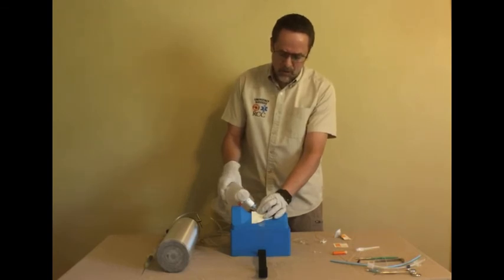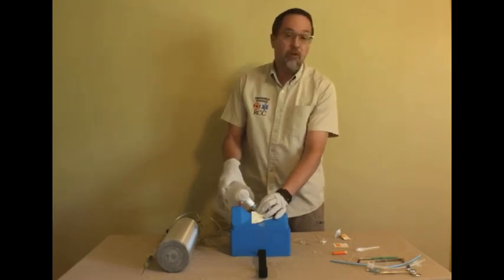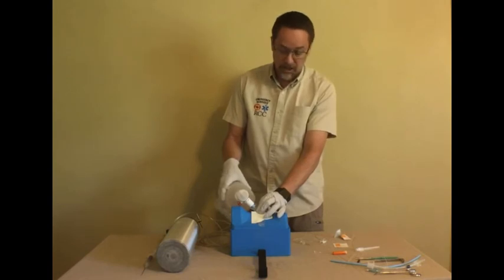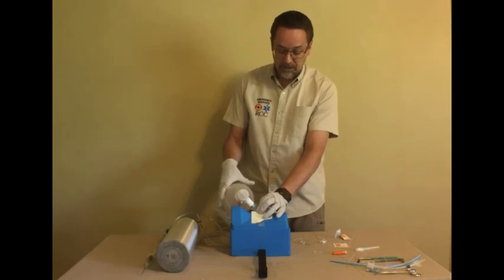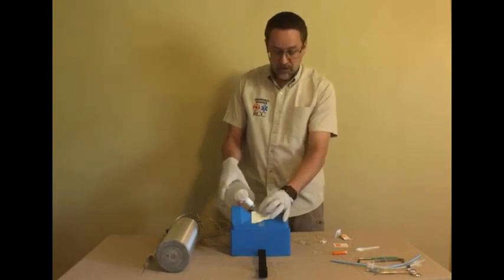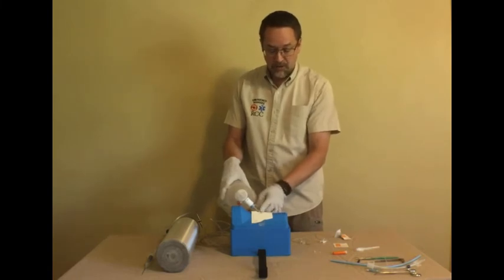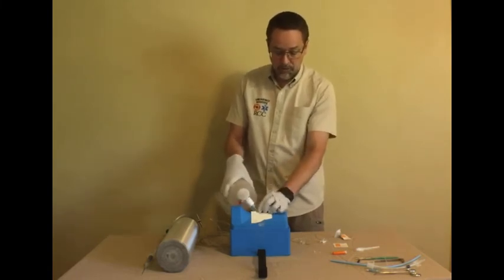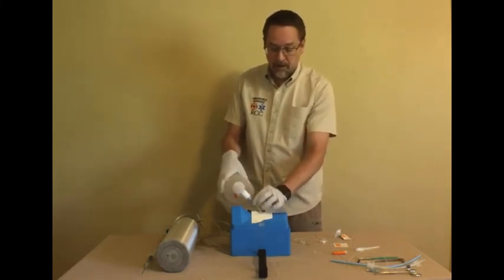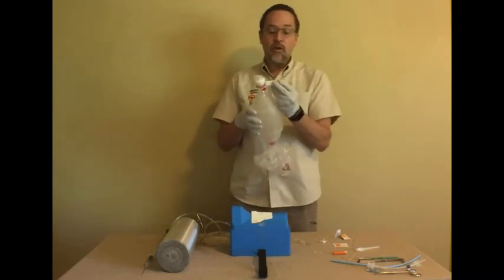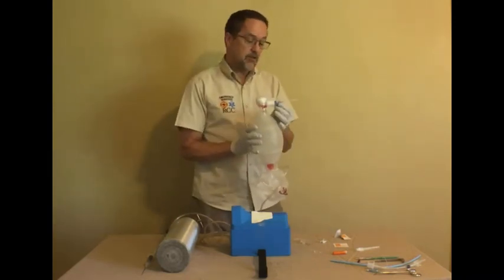So as you can note, it is difficult to push very much air through a 12 or 14 gauge catheter. Again, we need to do 1 second of inhalation and 2 full seconds to allow for exhalation. We also need to secure this device in a way that isn't going to allow it to bend or kink the catheter in order to make sure it's going to keep working. Now, I encourage you in your practice to test out this theory. You notice how small that catheter is.